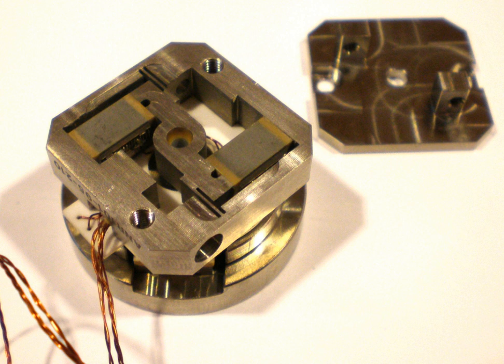The direct drive piezoelectric motor creates movement through continuous ultrasonic vibration. Its control circuit applies a two-channel sinusoidal or square wave to the piezoelectric elements that matches the bending resonant frequency of the threaded tube, typically an ultrasonic frequency of 40 kHz to 200 kHz. This creates orbital motion that drives the screw.